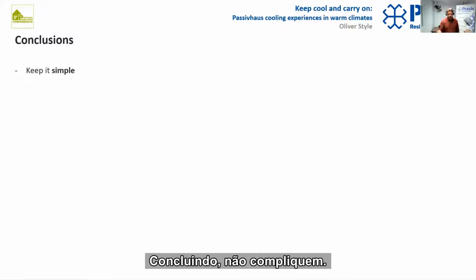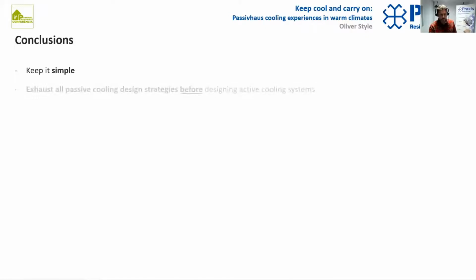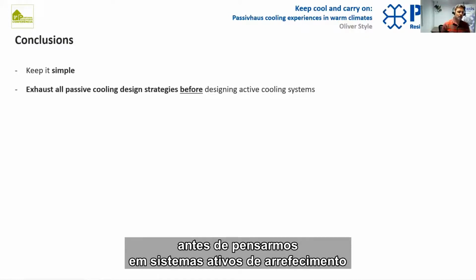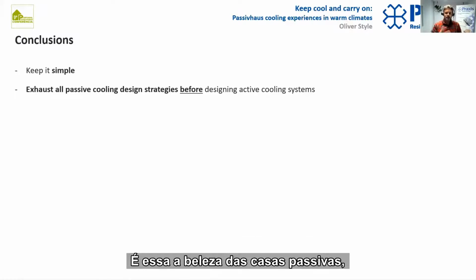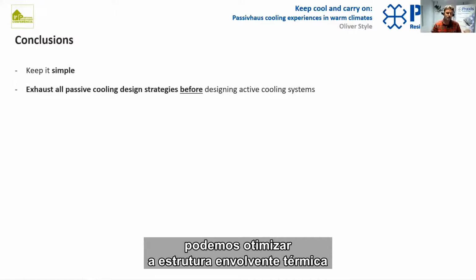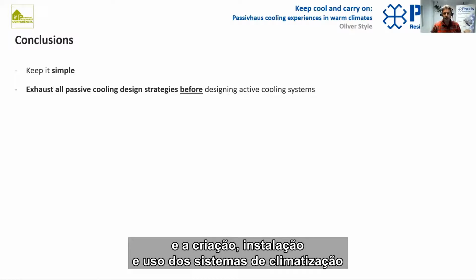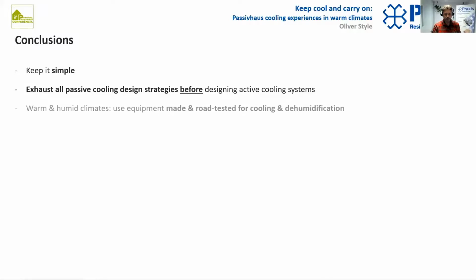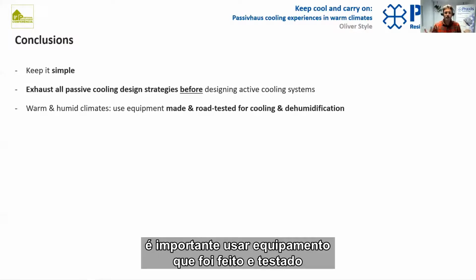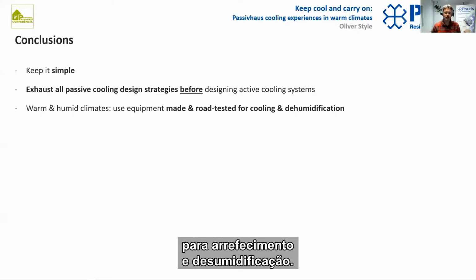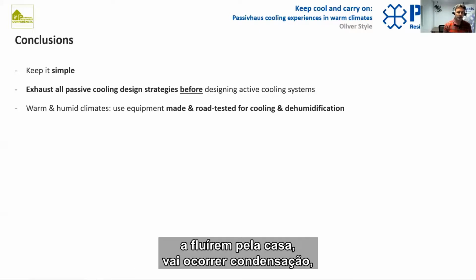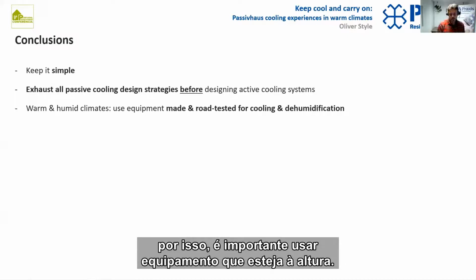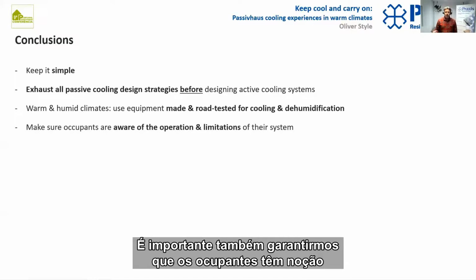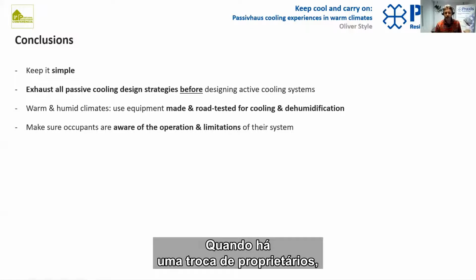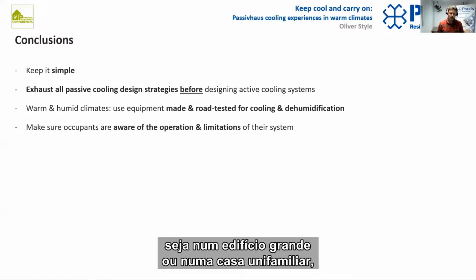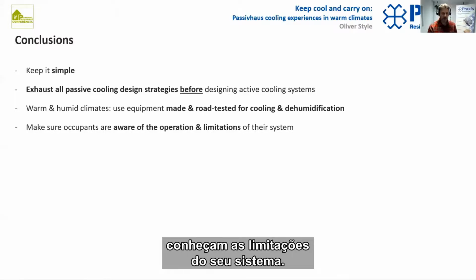So conclusions: keep it simple. That's one of the main things we've learned. Also important to exhaust all passive cooling strategies before we look at active cooling systems and air conditioning. That's the beauty of passive houses, to maximize and optimize your thermal envelope, and then your HVAC systems are simpler and cheaper to design, install and use. Right? So in warm and humid climates, it's important to use equipment that's really been made and road tested for cooling and dehumidification. When there's a lot of moisture in the air and you're running cool fluids around the place, condensation will happen wherever it can, and so it's important to use equipment that's really up to the job. I think also good to make sure occupants are aware of the operation and limitations of their system. So when there's a building handover, whether it's a large building or a single family home, important that the occupants or the managers of the building are aware of what the limitations of their system are.